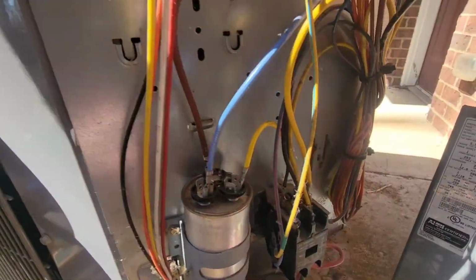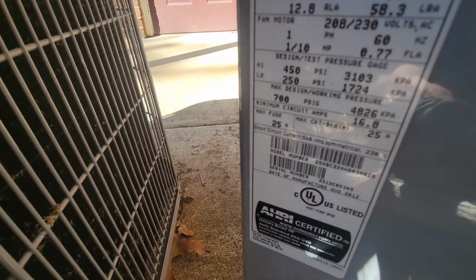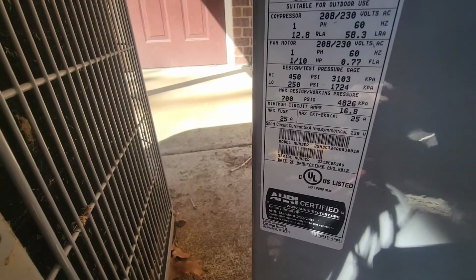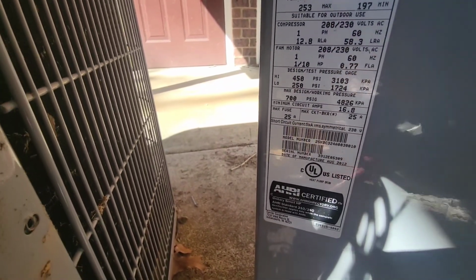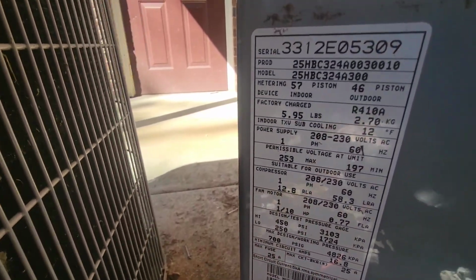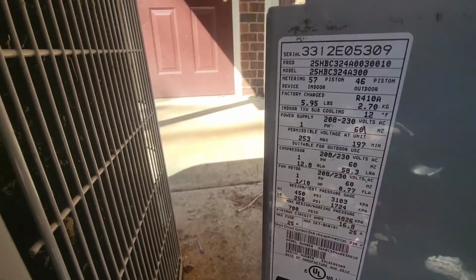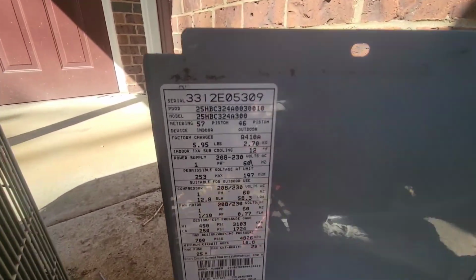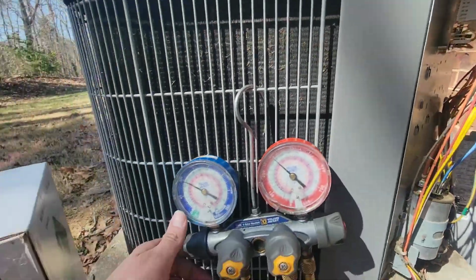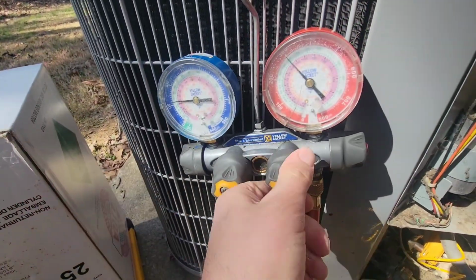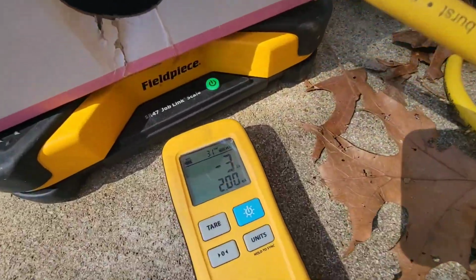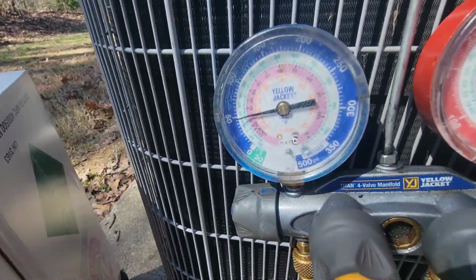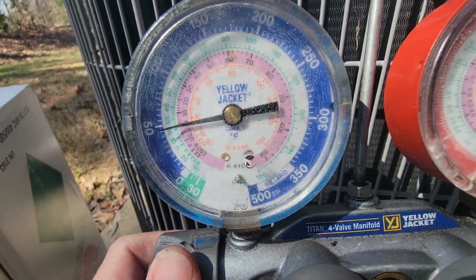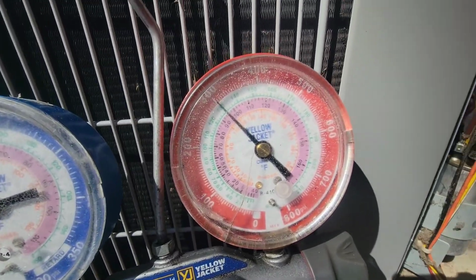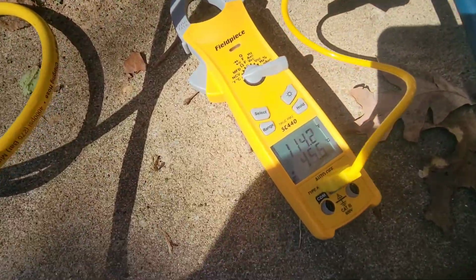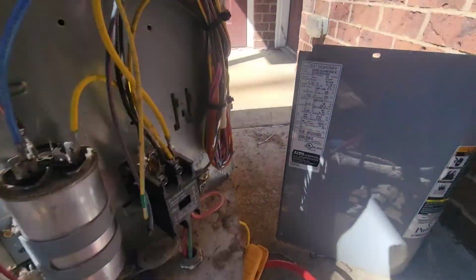See what this system holds. So, looks like our system holds 12 degrees of subcooling on the indoor TXV. 6 pounds is what the system holds. 5.95 pounds. And we've added 3 pounds of refrigerant now. 3 pounds, 2 ounces. Pressure is 45 and 300. Temperature on the vapor line is 114.